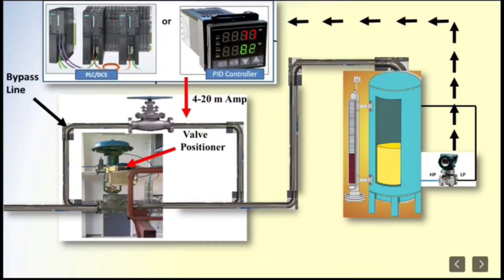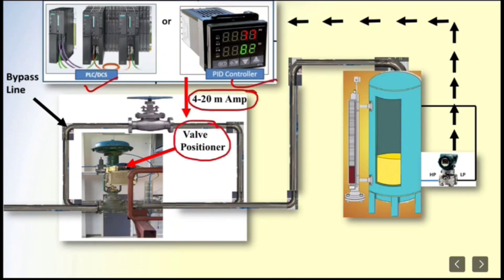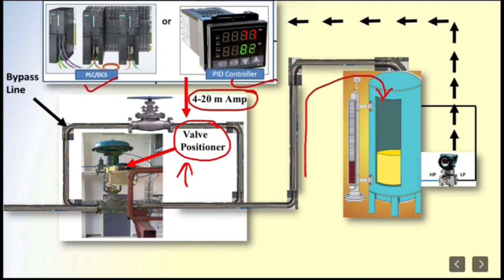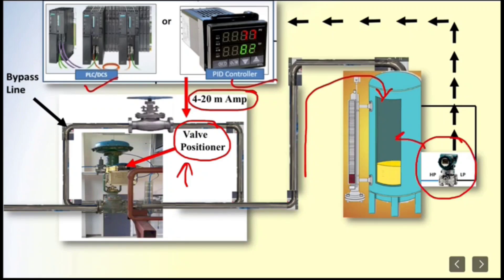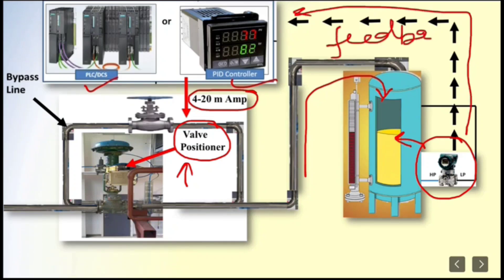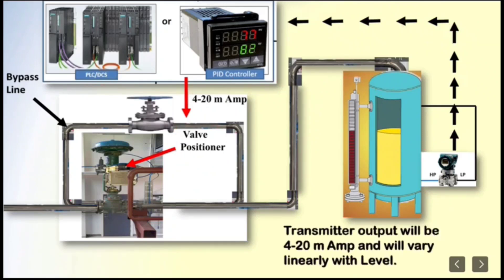Here we have shown a level control system. We will use a controller — PLC, DCS, or PID controller. From the controller, a 4 to 20 mA signal will be given to the control valve, and this signal is passed to the positioner. When the control valve operates, liquid will start going into the tank and filling it. To measure the level of that liquid, we have used a DP type transmitter, which will continuously keep measuring this level. The 4 to 20 mA signal will be sent back to the controller as feedback, and the output of the transmitter will vary linearly with the level.